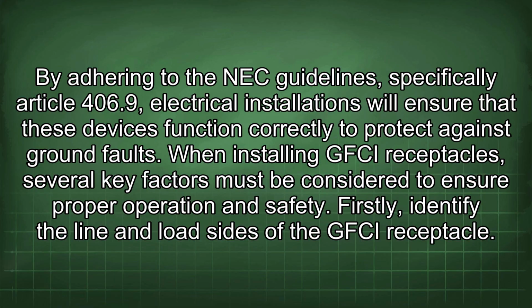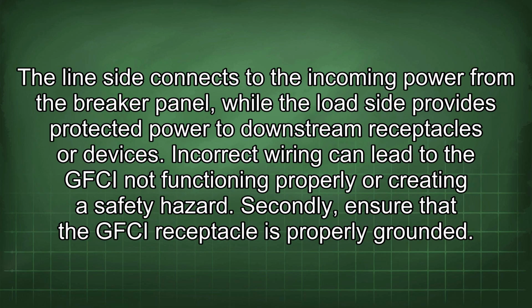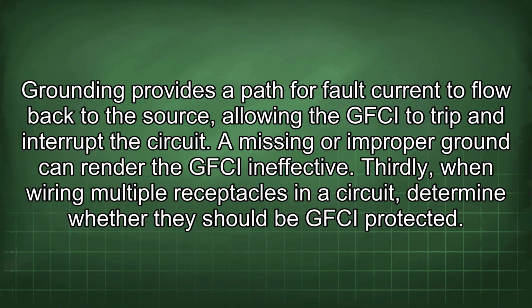Firstly, identify the line and load sides of the GFCI receptacle. The line side connects to the incoming power from the breaker panel, while the load side provides protected power to downstream receptacles or devices. Incorrect wiring can lead to the GFCI not functioning properly or creating a safety hazard. Secondly, ensure that the GFCI receptacle is properly grounded. Grounding provides a path for fault current to flow back to the source, allowing the GFCI to trip and interrupt the circuit. A missing or improper ground can render the GFCI ineffective.